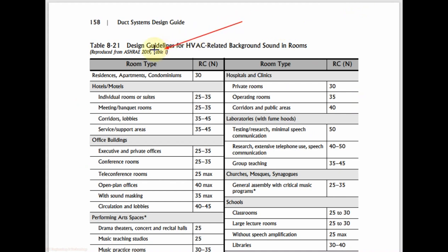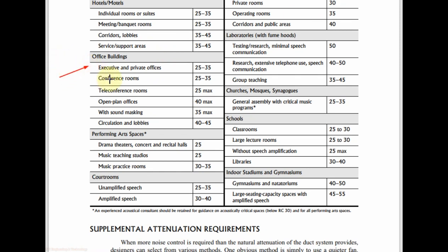As per ASHRAE 2019, the sound level for residence and apartment is maximum up to 30 NC. For motels, individual rooms or suite 25 to 35, meeting and banquet 25 to 35, corridors and lobbies 35 to 45, services and support areas 35 to 45.